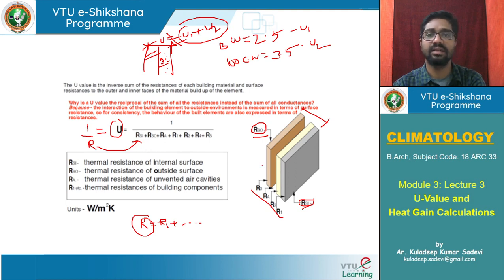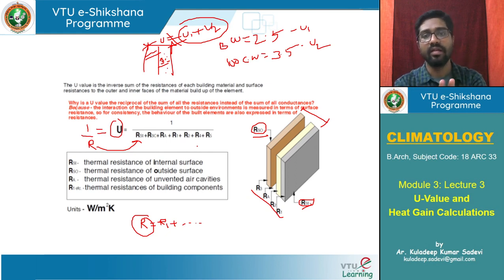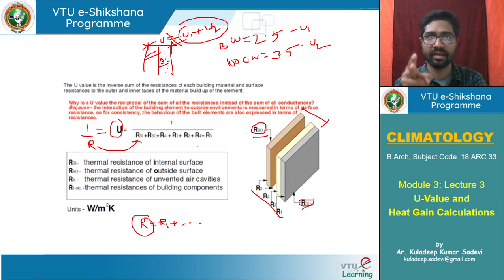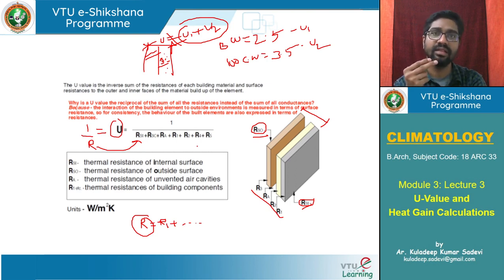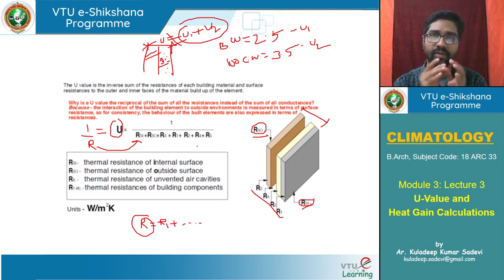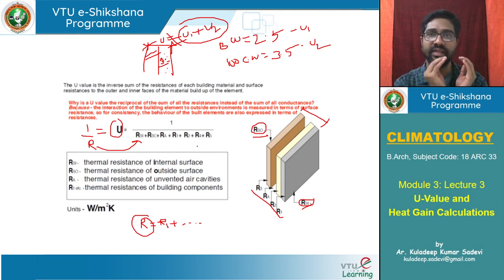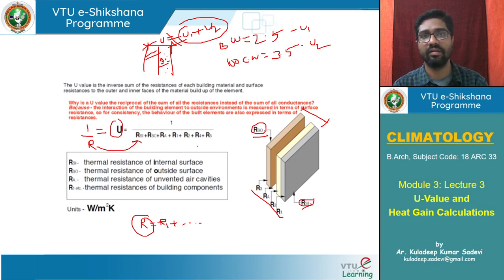This is the calculation procedure. If we know R directly, we add them and calculate U. If we don't know R, we need thermal conductivity K and thickness T — then R = T/K. Once we know R for all components, we add them: R1 + R2 + R3 + internal and external surface resistance. We get total R, and 1/R gives us U-value.